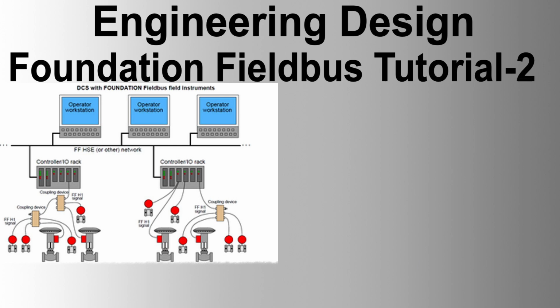Function block. What is a function block? A function block is a functional model common in measurement and control. It is a generalized concept of the functionality you have in field instruments and control systems, such as analog input and output, as well as PID control. The Foundation Specification, Function Block Application Process Part 1, gives fundamental concepts, while Part 2 and later give various function block details.